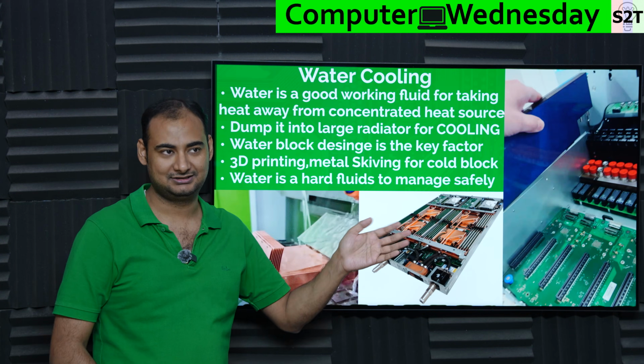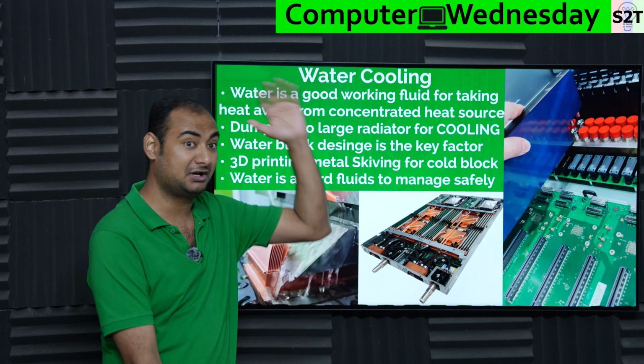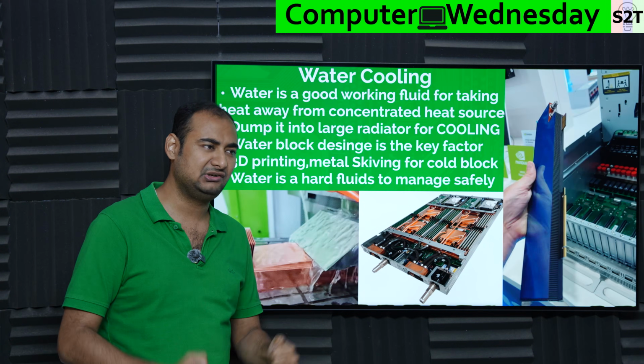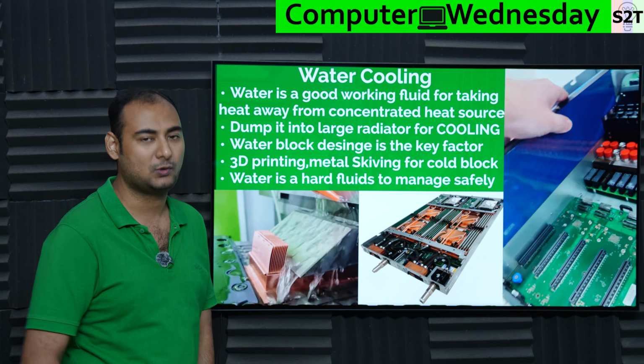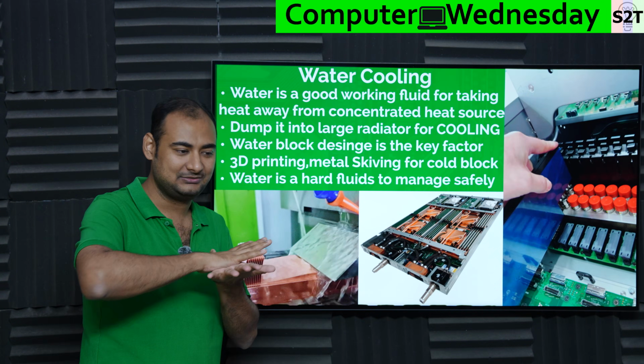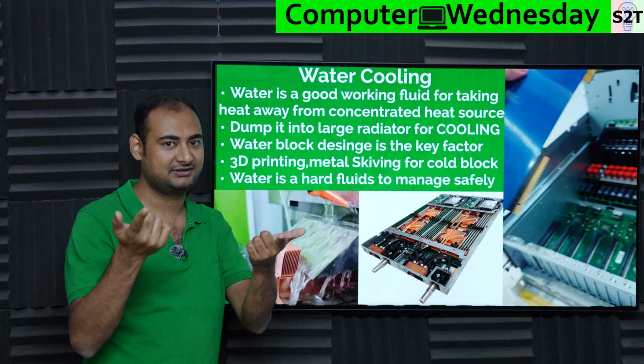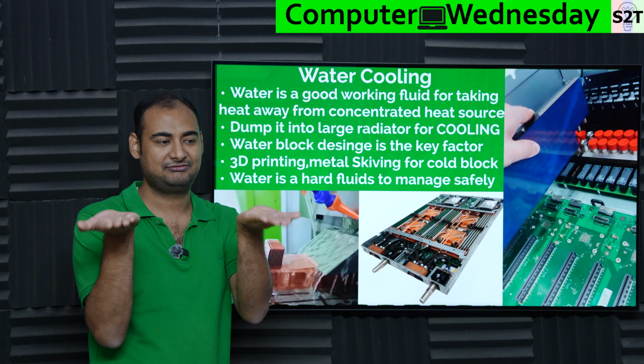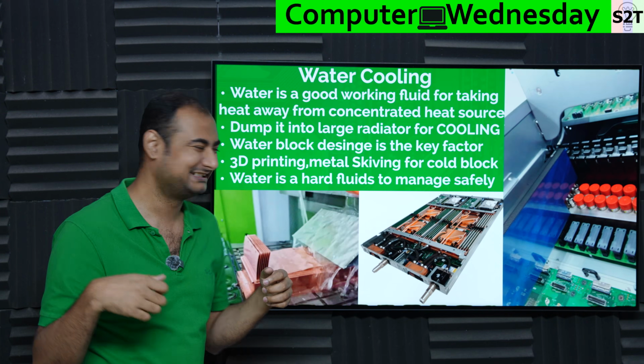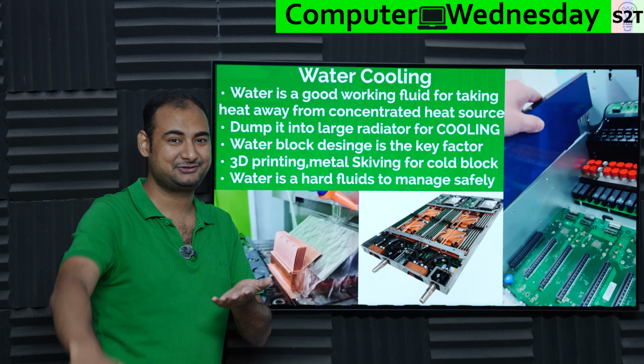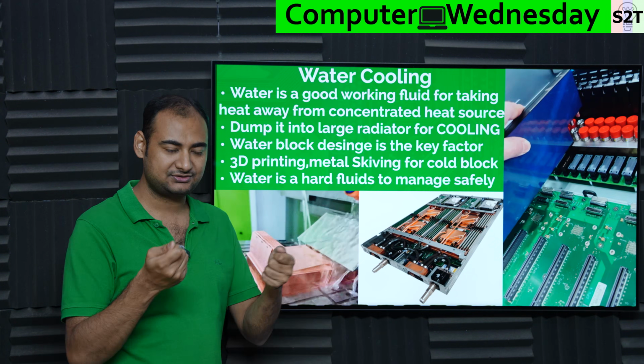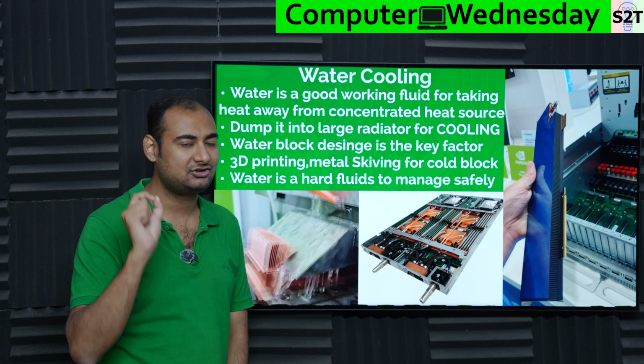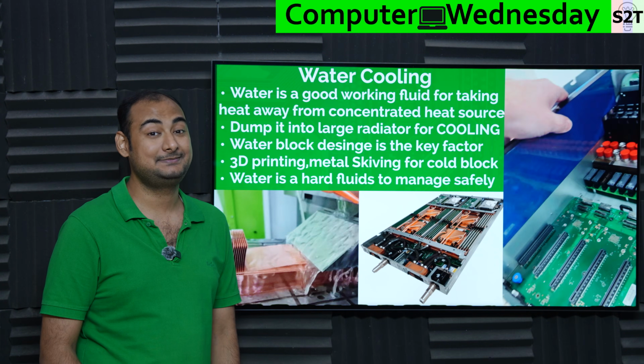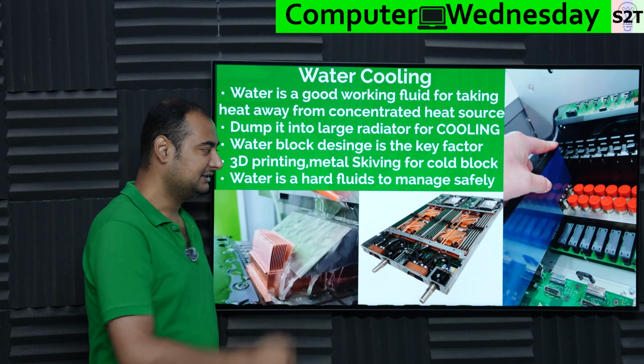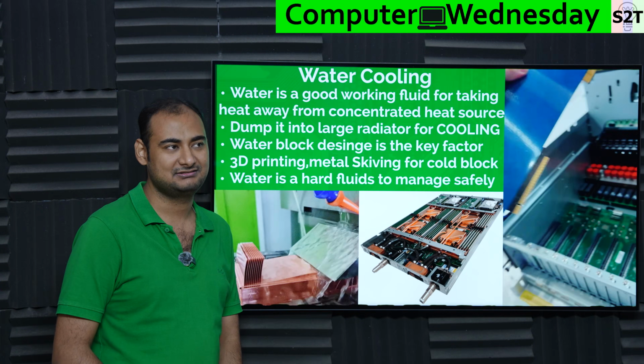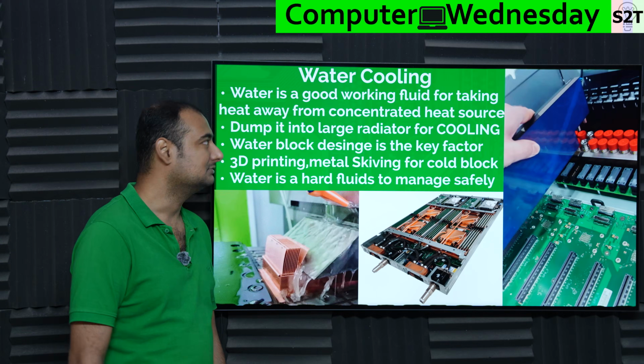That's how modern AI systems are reaching 40 kilowatts per rack, and somebody's trying for 100 kilowatts per rack. That's water only. At that point, you'll have a CPU that's fully flat, RAMs laid out flat. That's why NVIDIA's RAMs are not socketed, they're flat slot, they have to be, otherwise they won't be able to cool it. So everything will be flat and you just put a liquid plate on it, with connectors that let you connect and disconnect without a single drop of water leaking. That's expensive, water is a harder thing to do. That's why the likelihood of you seeing this sort of thing in your household is zero, they are very expensive. So this is water cooling.